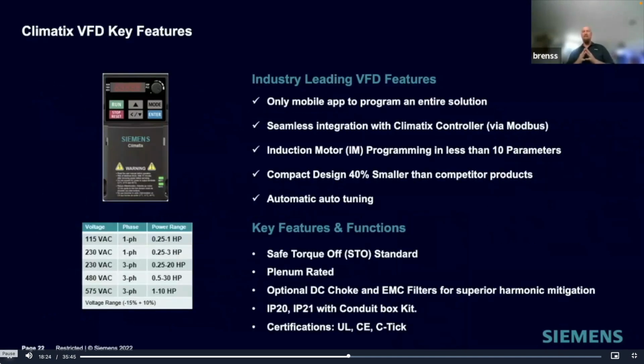Let's talk a little bit about our VFD. It's an industry-leading VFD with the features. The only mobile app program to use the entire system. That's right, we control this VFD from our mobile app, and it's a one push button. Seamless integration with the Climatix controller via Modbus. We've taken all the points in the VFD and built them all into the controller. So when you're on our cloud, you can see all those points and manipulate them if you want to, but they're all preset in the controller.